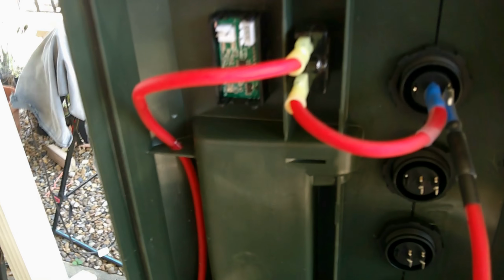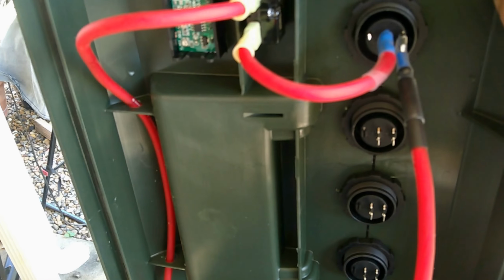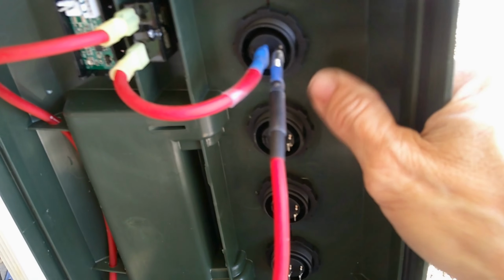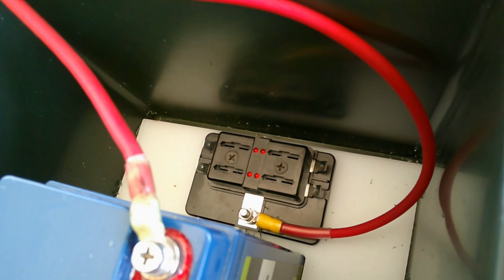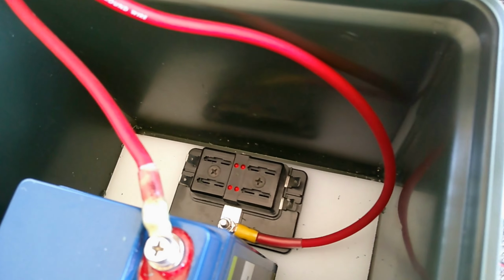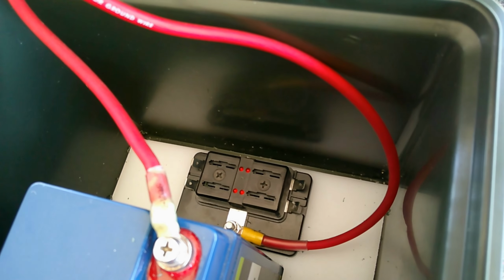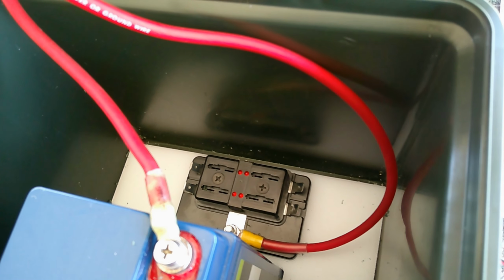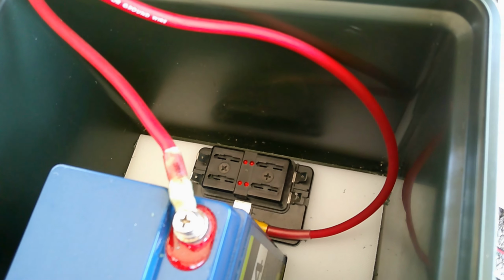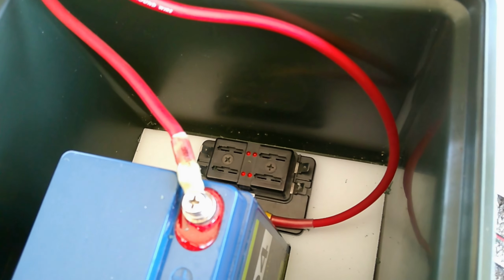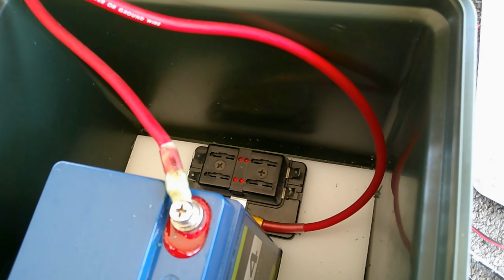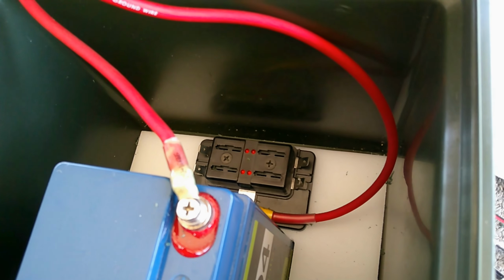For positive, coming off the battery, it comes up here to the circuit breaker - that's the very first and main level of protection. Then it comes out of the circuit breaker over here, over to the cutoff switch, and from there back down to the power distribution panel. I've pretty much determined there will be one 2 amp circuit to run the LED light strips, and the other 3 will be 20 amp fuses that I'll make use of down here.